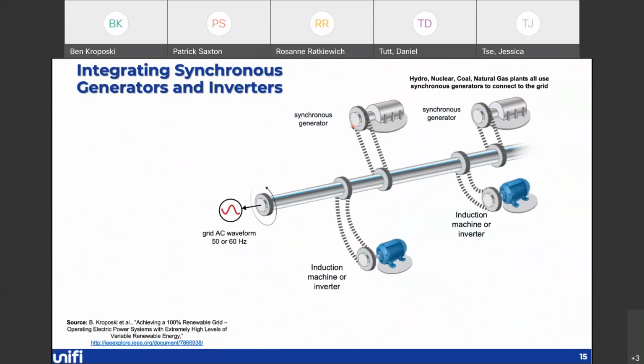So this is the big power grid, but it could be a microgrid. But in general, when we interconnect the Western Interconnect of the United States, we are electrically tying synchronous generators that are in hydro plants, nuclear, coal, natural gas, all together through the electric power grid to create basically a large virtual machine. And what that means is that if, for example, you have a problem where one of your generators drops out, this generator will pick up that load automatically.